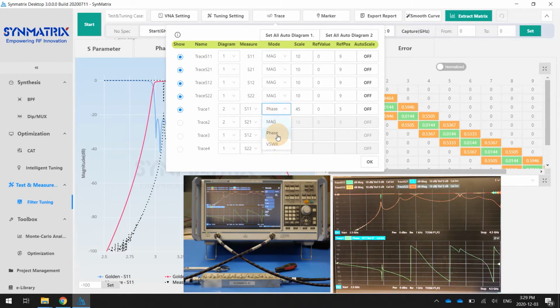Of course, the user can show the VSWR, and also we can change the scale to 0.1 to get more details. Okay. Because the VSWR is now too bad, so set up 2 and maybe 4. Yeah, as you can see, the user can easily set up these scale numbers here. Okay, so fully control the VNAs.